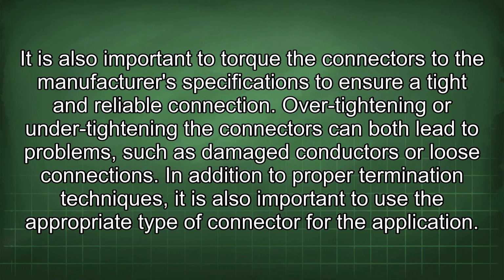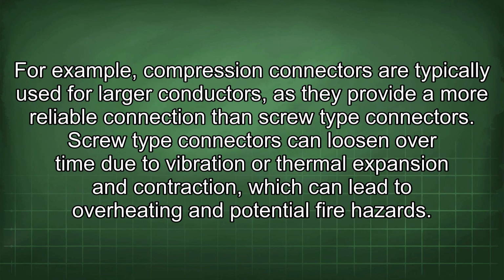It is also important to torque the connectors to the manufacturer's specifications to ensure a tight and reliable connection. Over-tightening or under-tightening the connectors can both lead to problems such as damaged conductors or loose connections. In addition to proper termination techniques, it is also important to use the appropriate type of connector for the application. For example, compression connectors are typically used for larger conductors, as they provide a more reliable connection than screw-type connectors.